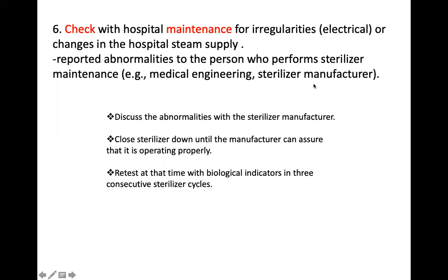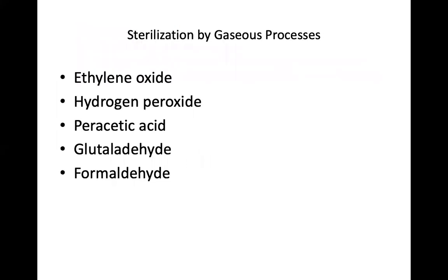The manufacturer, usually the people who supply these things carry out maintenance, okay? So discuss these abnormalities, close down the sterilizer until the manufacturer can assure you that it is operating properly. And once you have got this assurance that it is operating properly, carry out a biological indicator test in 3 consecutive cycles to make sure it is now okay. It is now safe for use, okay?